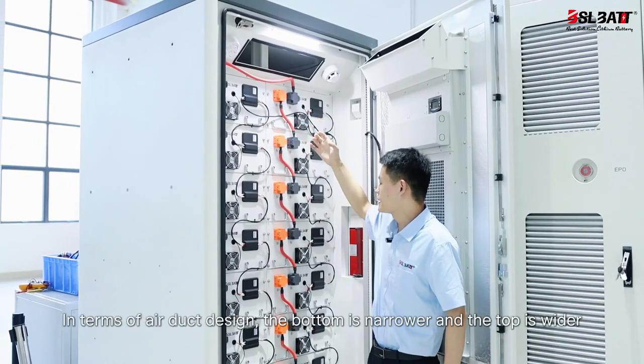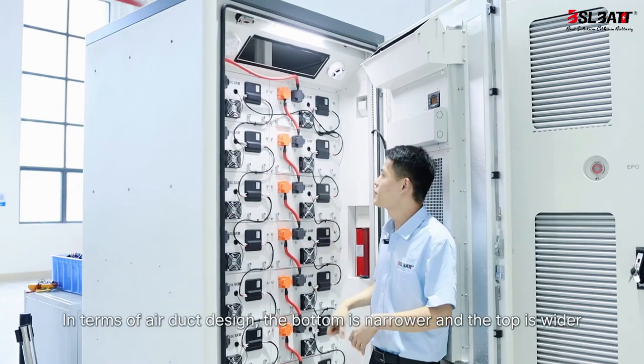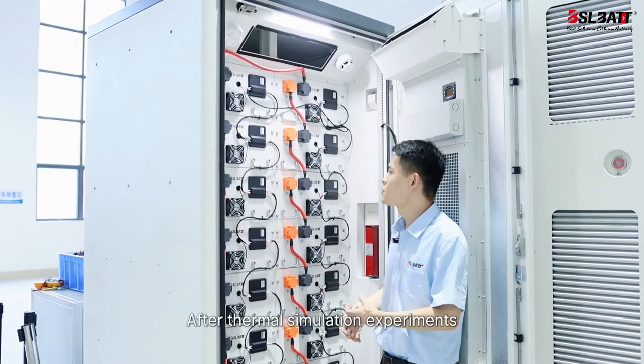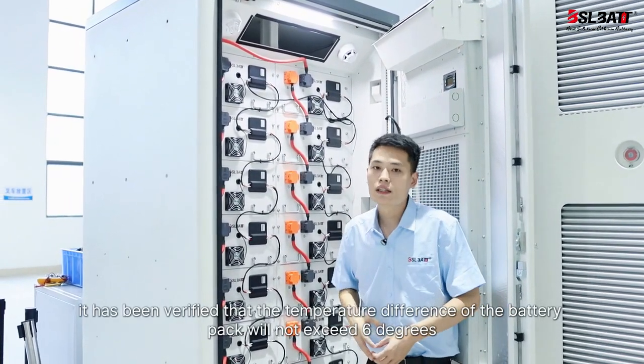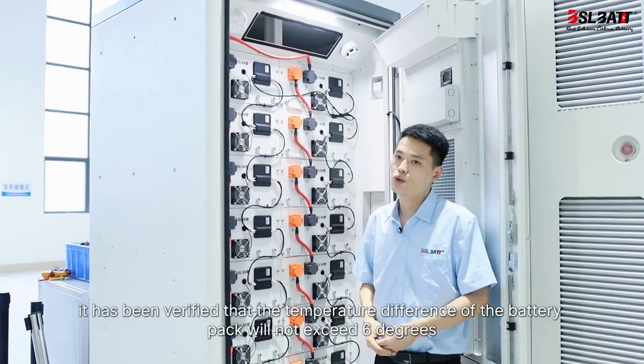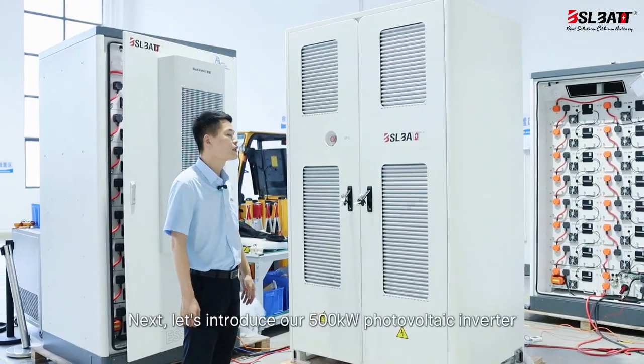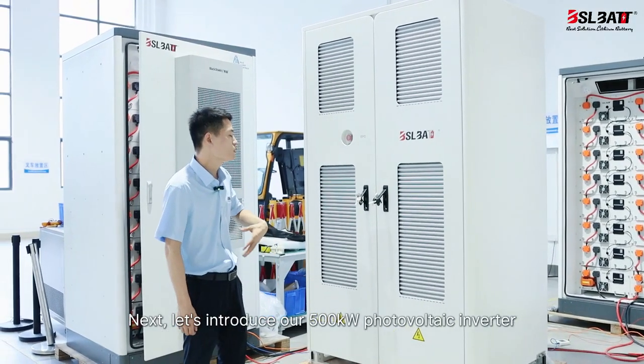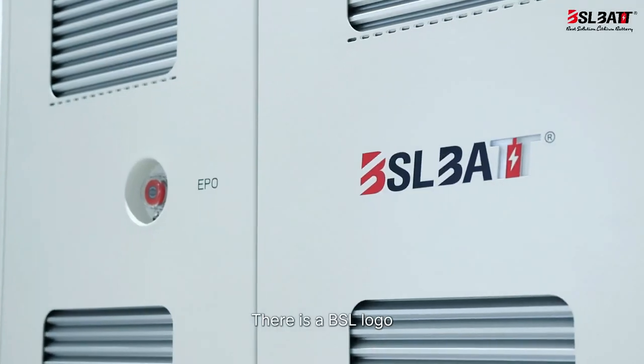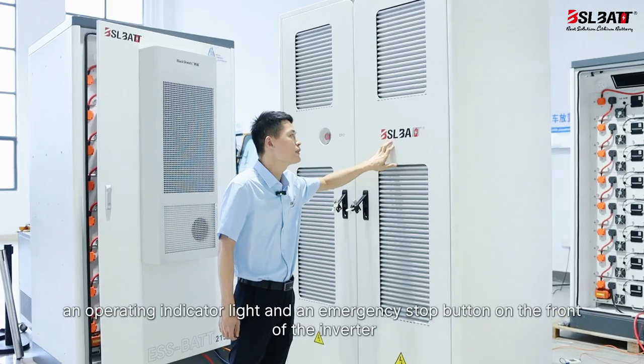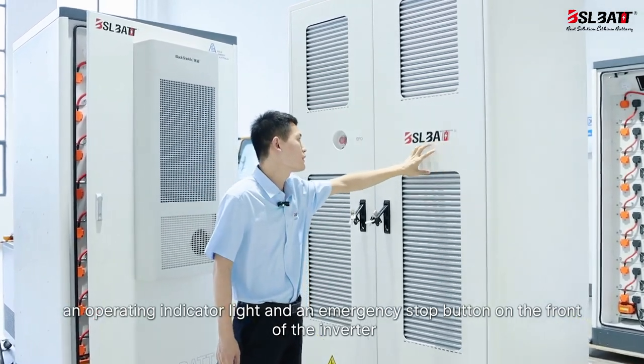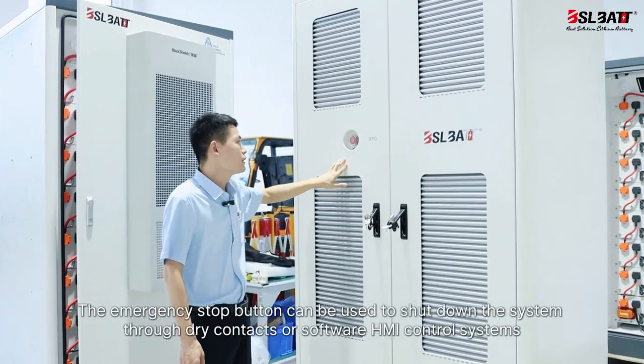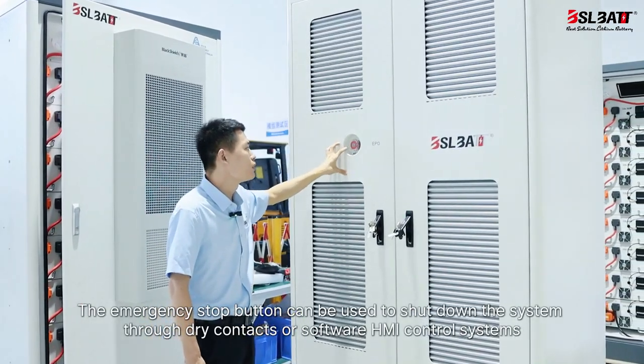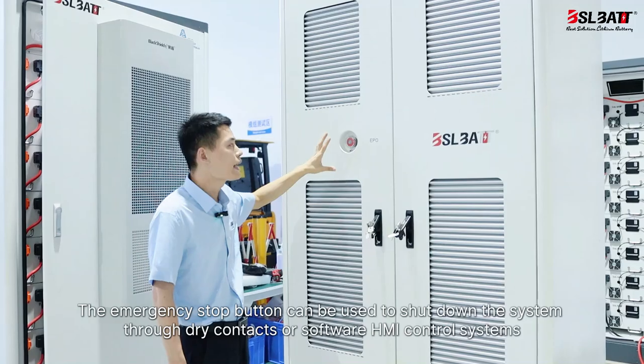In terms of air duct design, the bottom is narrower and the top is wider. After thermal simulation experiments, it has been verified that the temperature difference of the battery pack will not exceed 6 degrees. Next, let's introduce our 500 kilowatts photovoltaic inverter. There is a BSL logo, an operating indicator light and an emergency stop button on the front of the inverter. The emergency stop button can be used to shut down the system through dry contacts or software HMI control systems.